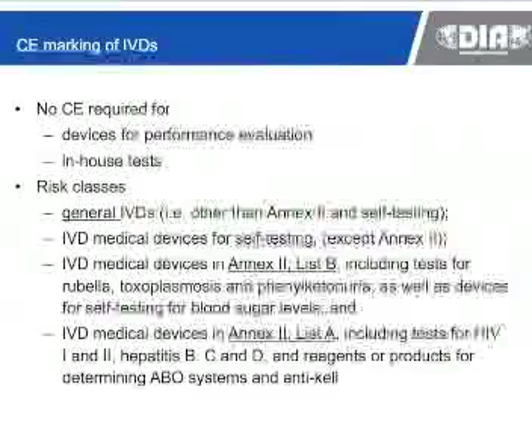There's IVDs for Annex 2 List B indications. That includes tests for toxoplasmosis, amongst other things, but it also includes devices for self-testing of blood sugar levels. So the self-testing example I just gave was a bit misleading because they are called under Annex 2 List B and not general self-testing. IVD medical devices in Annex 2 List A include, for example, the really risky ones like HIV, hepatitis, and so on. So the risk class determines the level of scrutiny in conformity assessment.